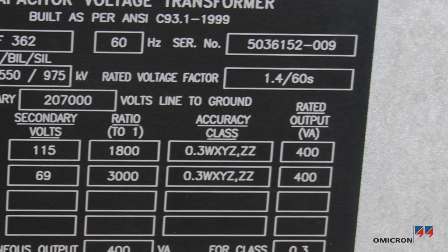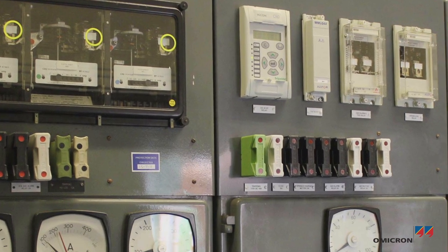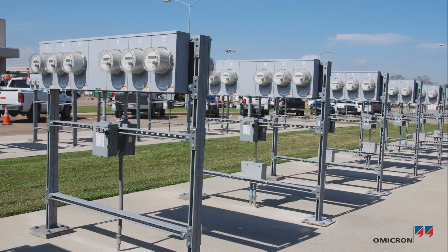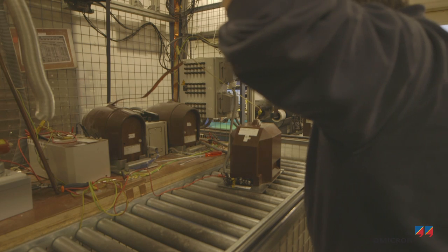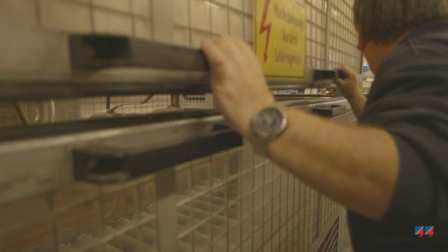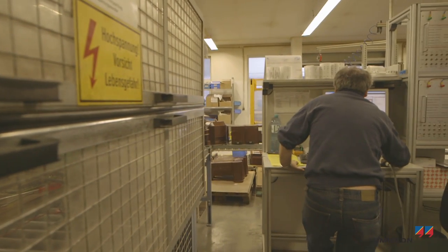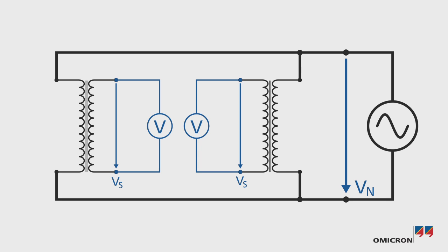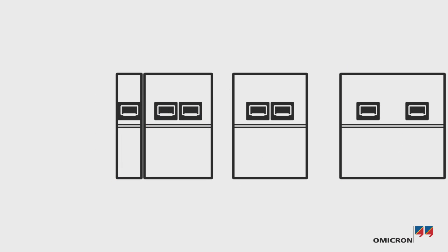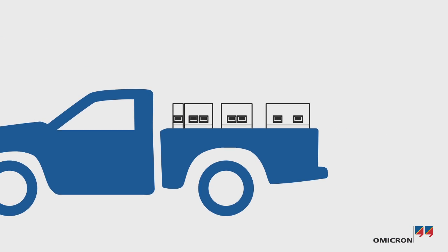The accuracy of the voltage transformer is important for a reliable electric power supply and correct revenue metering. Since the beginning of the 20th century, accuracy measurements have been performed at nominal voltage. During these measurements, the secondary voltage of the transformer is compared with the secondary voltage of a highly accurate reference transformer. Over time, these conventional approaches have been adopted for mobile use.